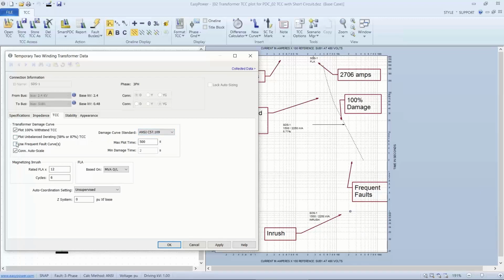If we want to show the frequent fault curve, again, the 100% damage curve is the straight line, and that's something we don't want to exceed at any point in time. If we apply the frequent fault curve, you see it takes the recognized Z curve, and so the frequent fault is this lower section, and the vertical bar is just the connection between the two plots. And then if we're going to be considering a single line to ground fault on the secondary from equipment in the primary or protective devices in the primary, we plot the unbalanced derating curve, and we get our second derated plot.